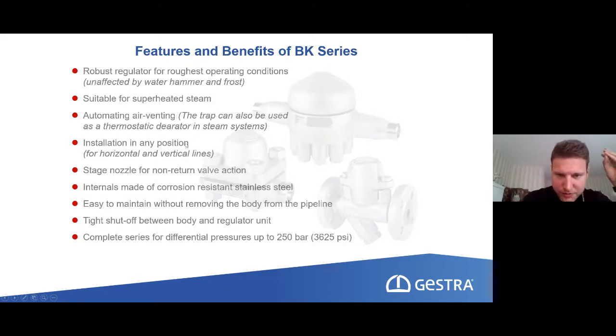Installation in any position, so we can have it in vertical and horizontal installation, which is very good. The stage nozzle works as a non-return valve. If we might have a backflow of condensate, to prevent this we have a non-return valve integrated.